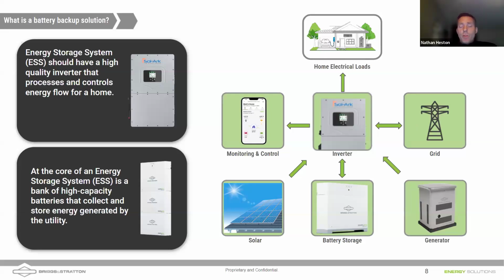But a whole home inverter like this Sol-Ark 15k can also incorporate a generator. And so if the solar is unavailable, or if solar is not even attached to the system, in a grid down event, the inverter can pull power from a battery to cover the home's loads. And if that battery gets low, we can charge the battery by starting up a generator, using that to cover the home's loads and to charge the battery up. And we can program how quickly we want to charge the battery. So there's a lot of control in these systems.